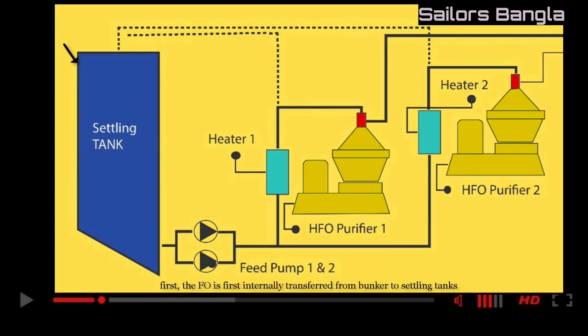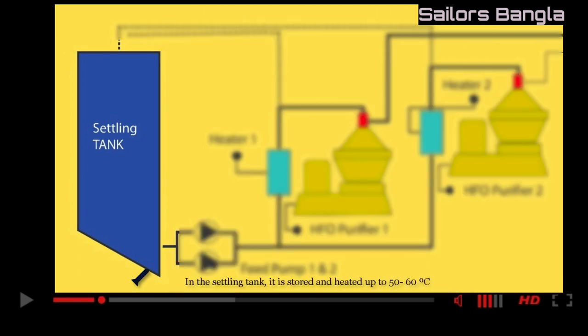First, the fuel oil is internally transferred from bunker to settling tanks. In the settling tank, it is stored and heated up to 50 to 60 degrees Celsius to separate it from water, which is drained off from the bottom.